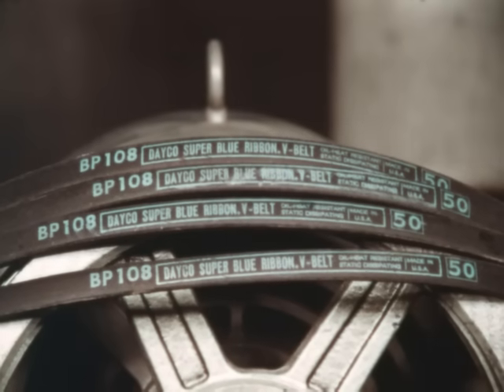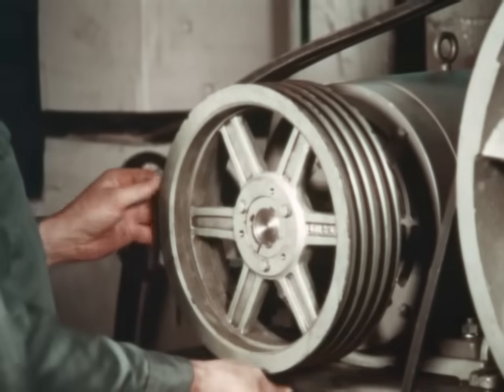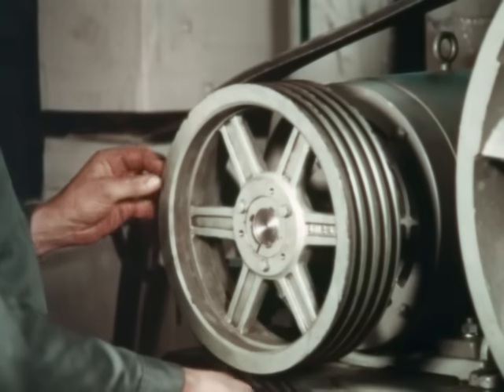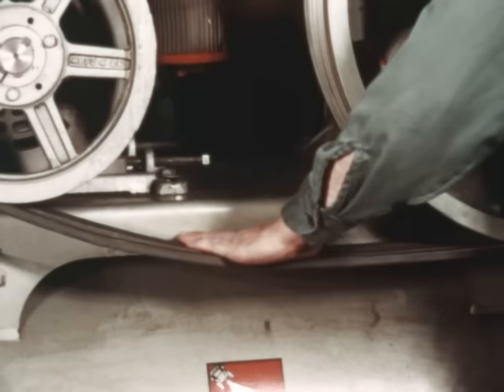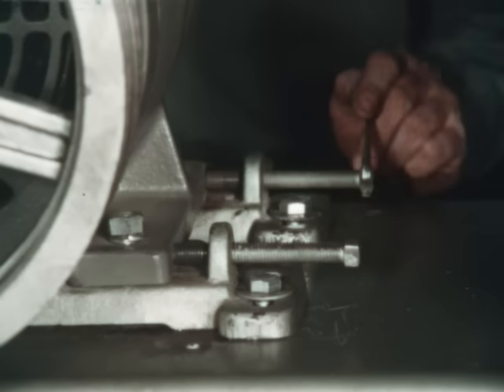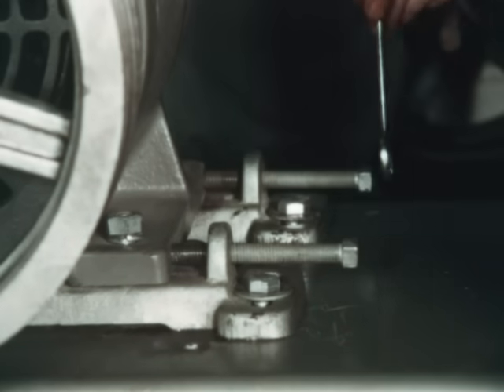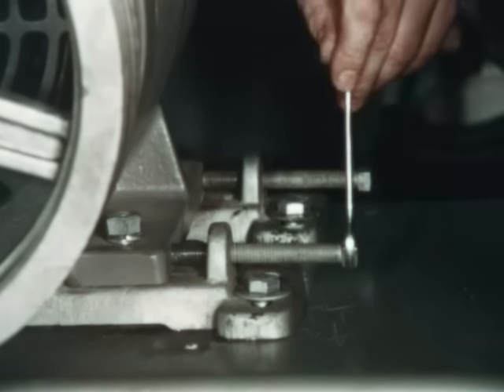Take the properly marked and matched set of belts and install them by simply placing them over the sheave grooves. Allow for the motor mount to be loosened sufficiently so that no force is needed to put the belts over the sheaves. Arrange the belts so that all the slack is on one side. Loosen the motor hold down bolts, then tension the belts by increasing the distance between the two shafts until the top and bottom spans of the belts are snug.